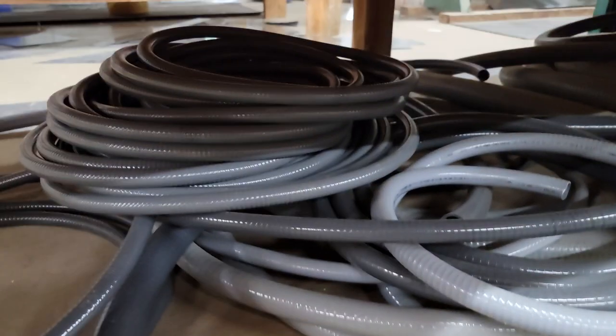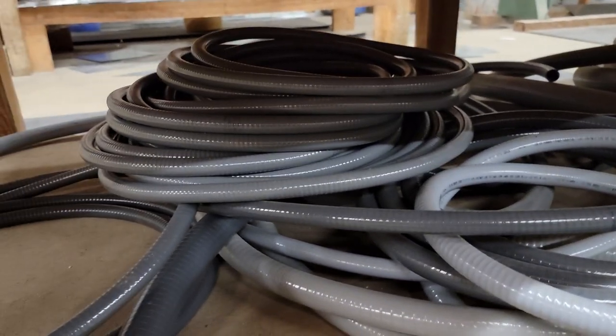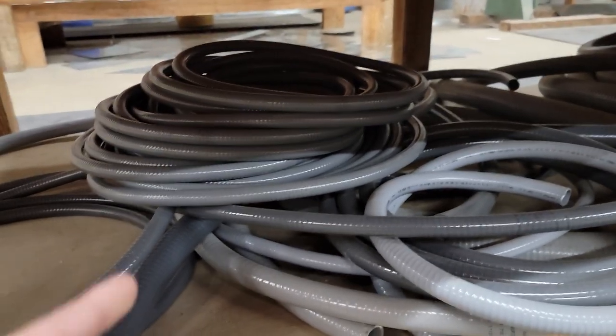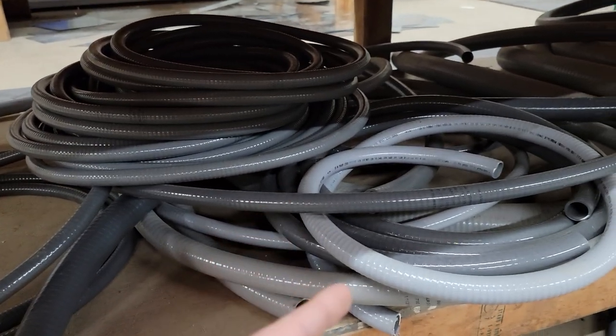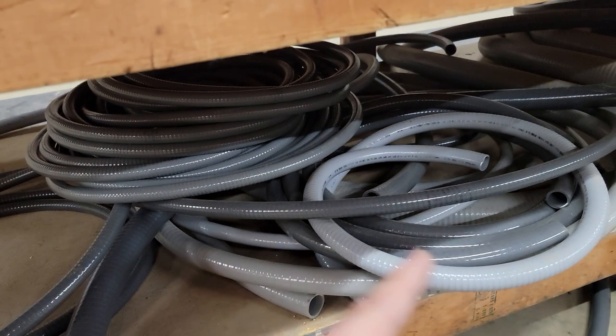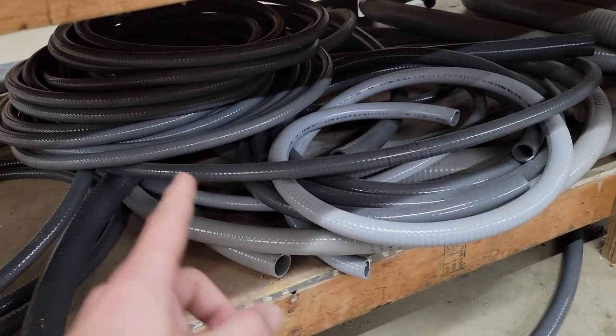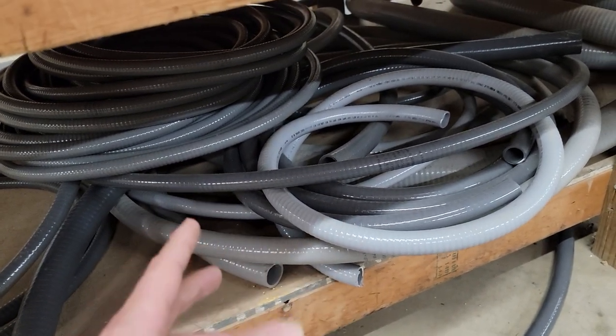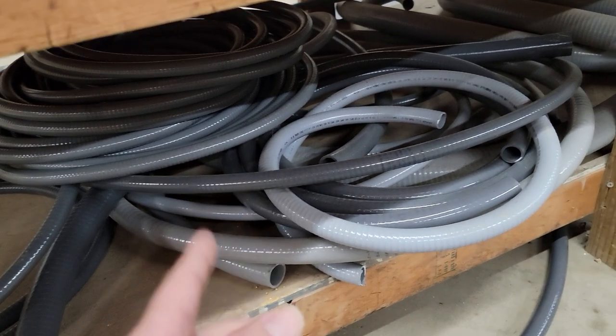You definitely need some liquid tight conduit, and this right here is half inch. You got 3/4 in there and 1 inch. Mostly you're going to be dealing with 1/2 inch and 3/4, okay? If it's only residential. So you'll definitely need to know that. You need to carry that with you.